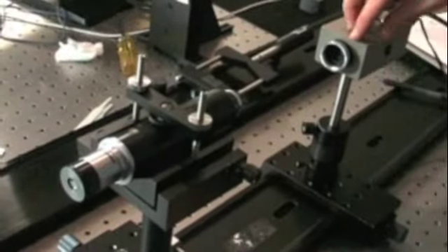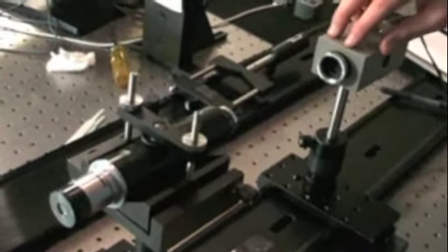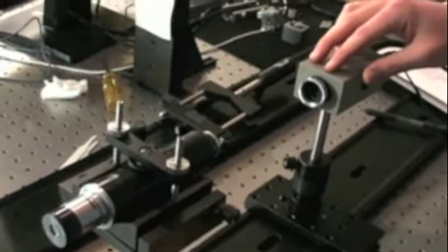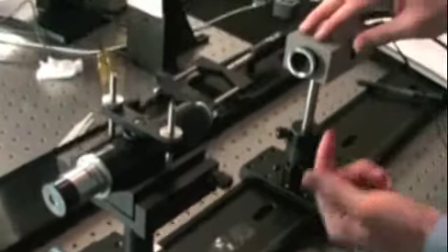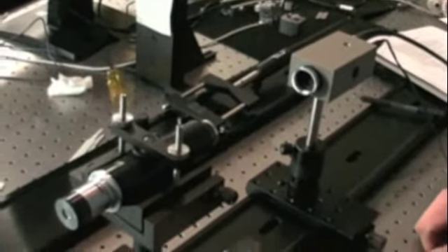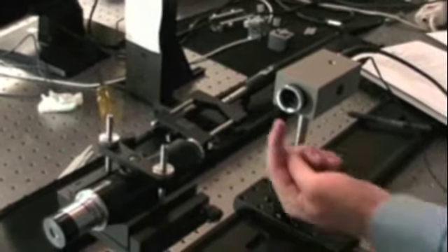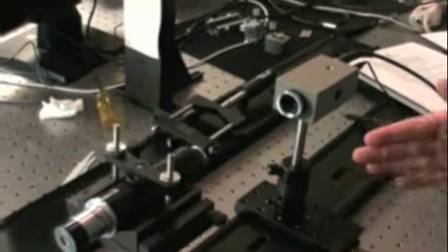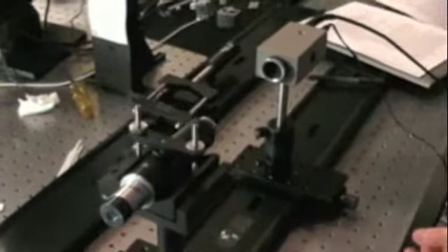So first, we're given a detector here, a CCD, and the first goal is to get the pixel size and the sensor dimensions. So we're using a microscope with a very low numerical aperture here, and you essentially just focus until you can see the physical CCD detector. And then you align the crosshair using this translation stage until you're on one edge of the detector, and then simply mark the reading, translate the microscope until you're on the other edge of the detector, and then that's your detector size. It's a very one-to-one translation.